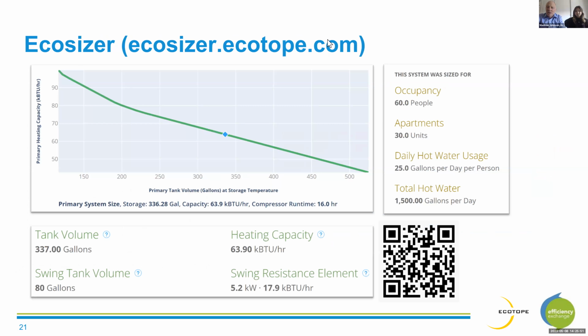The EcoSizer is a free online tool that Ecotope created with support from a couple of California utilities primarily, Southern Cal Edison and Sacramento Municipal Utility District, as well as from NEEA. And this is a program that allows for optimizing the sizing of the heat pumps so that the heat pumps run for 16 to 20 hours a day, and the storage is sized so that it can carry the buildings through those peak demand periods instead of relying on quick recovery, which is what most gas systems have been designed around.